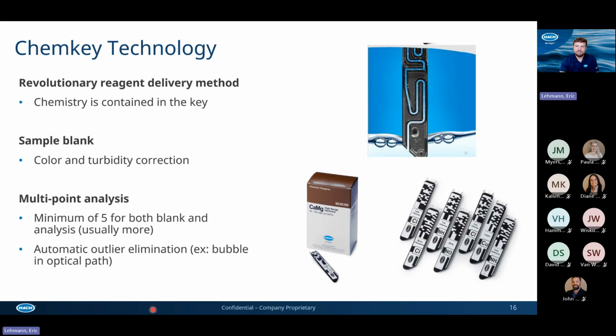It does a multi-point analysis on each sample. It's going to take a minimum of 5 readings, one for the blank, one for turbidity correction, but then it's going to throw out any outliers. So maybe you have bubbles in the sample or bubbles were drawn up into the instrument itself. It's going to detect that and throw those out and then give you an average or a calculation of those other 4 readings.